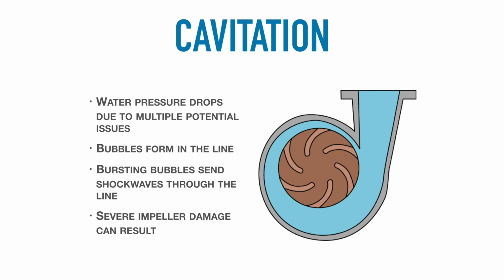So what I recommend is, one, make sure you don't have any water or air leaking into your system. You want only water running down in there. And if you hear an uneven sound or a sloshing sound going on inside of your motor and your pump when you get into your pump room, make sure you shut that system down and detect exactly where that issue is coming from, because you want to stop it before it gets too far. Unfortunately, you cannot replace that metal component that connects the impeller to the motor. You just have to replace the entire motor, which is a really, really big bummer. So we're looking to watch out for cavitation.